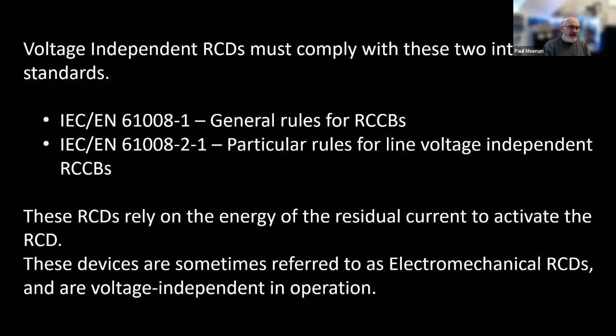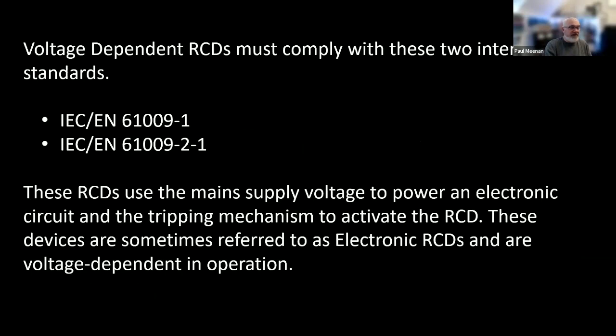and we have to configure them correctly as well as our earthing. Now, there's two types of RCDs I just wanted to skip through. Voltage independent must comply with the International Standard 61008, parts 1, 2, and 1. These RCDs rely on the energy of residual current to activate the RCD. So the leakage current, that residual current, is what activates it. They are often referred to as the old clunky electromechanical RCDs, and they are voltage independent in operation. Then we have voltage dependent, and they require compliance with 61009, 1, 2, and 1. These RCDs use the mains voltage to power an electronic circuit and the tripping mechanism to activate the RCD. So they're referred to as electronic RCDs and are voltage dependent.